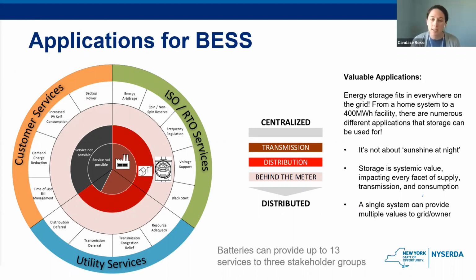Next is the frequency regulation. This is the immediate and automatic response of power to change in locally sensed system frequency, either from a system or from elements of the system. Regulation is required to ensure that the system-wide generation is perfectly matched with the system level load on a moment-by-moment basis to avoid spikes or dips, which can create grid instability. Then it's also utilized for voltage support, which ensures reliable and continuous electricity flow across the power grid.